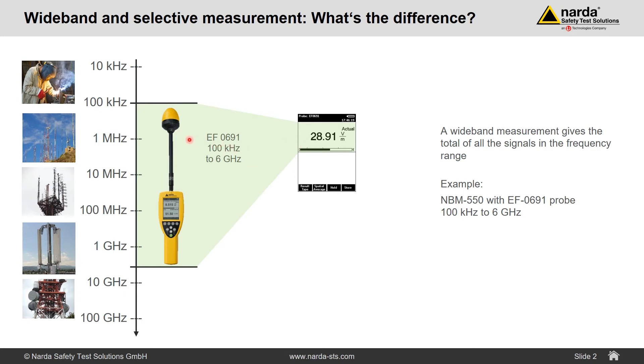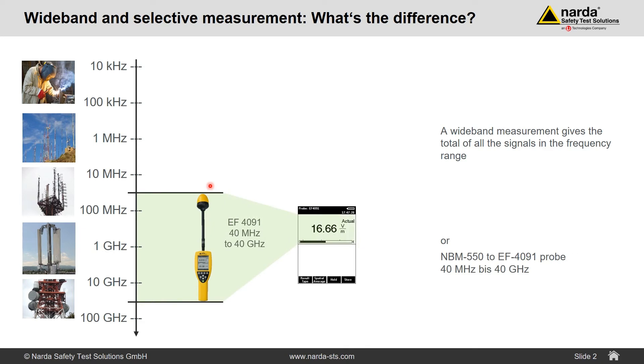The NBM cannot distinguish whether the signal comes from a television transmitter, longwave, or mobile radio — it only tells you, for example, 28.91 V per meter. If you want to change the frequency range, you connect a different probe. Like in our example here, we connect an EF4091, which covers a frequency range of 40 MHz up to 40 GHz, now also covering the point-to-point connection. It tells you that in this frequency range we have an amplitude of 16.66 V per meter.